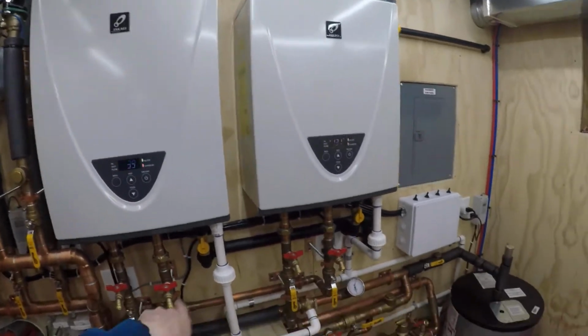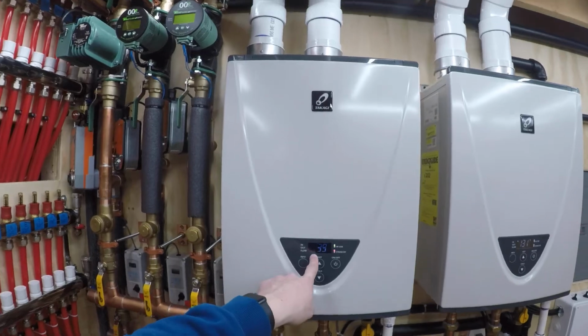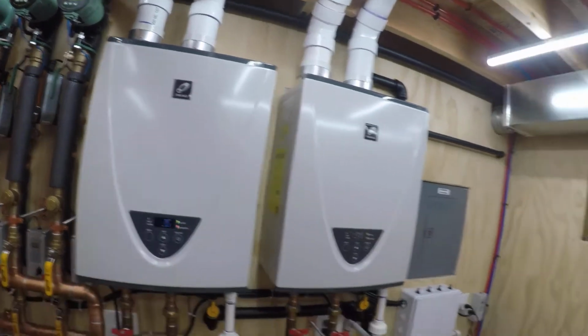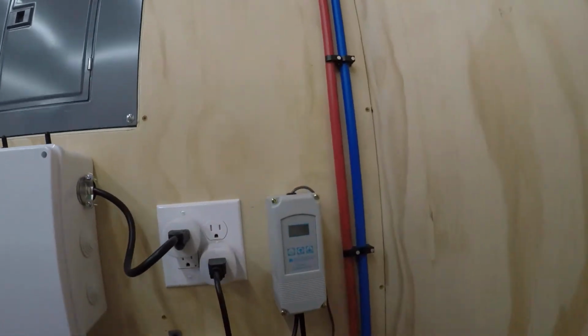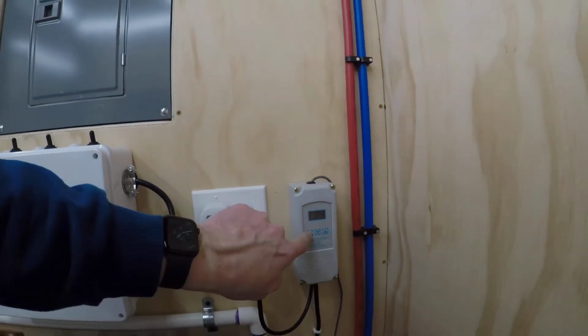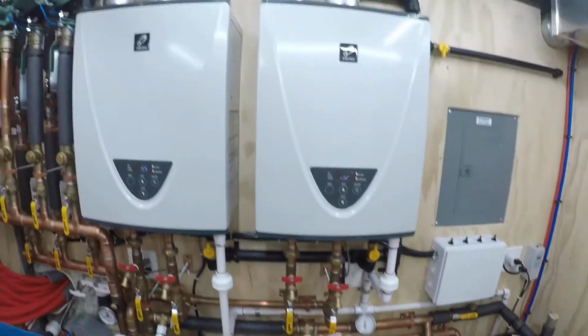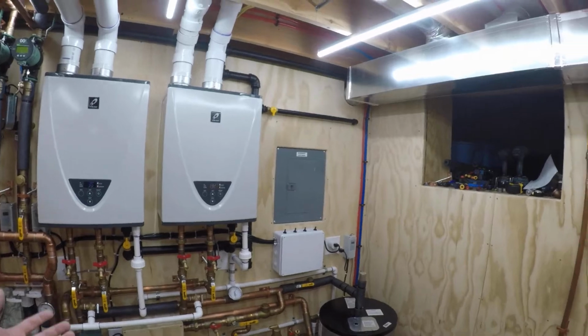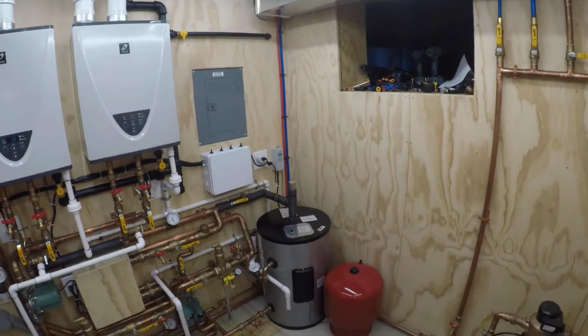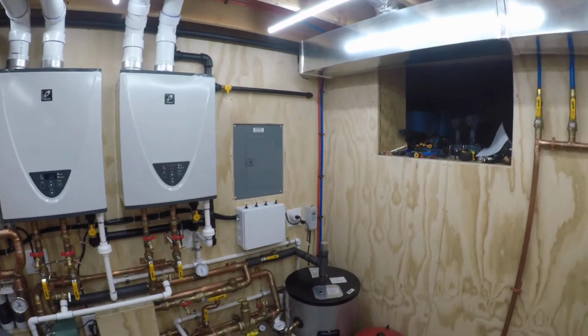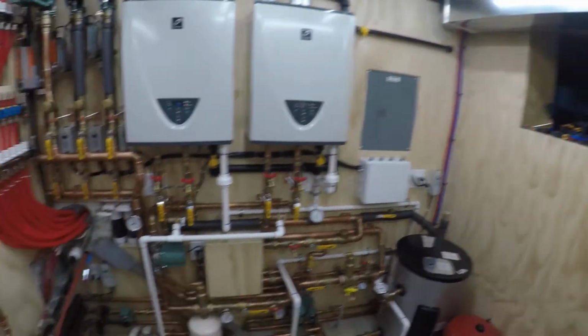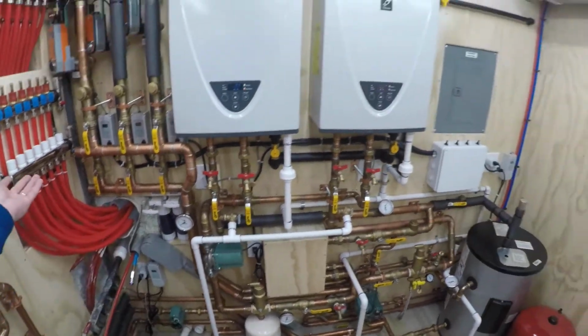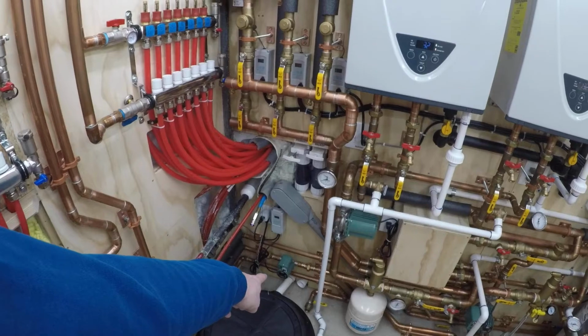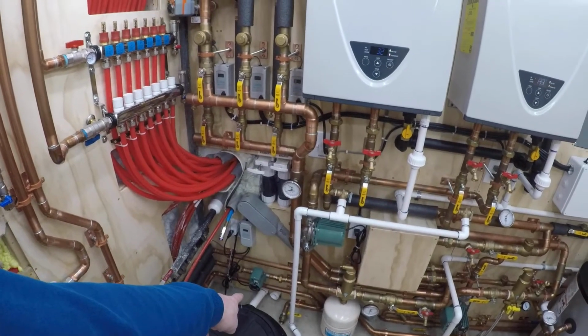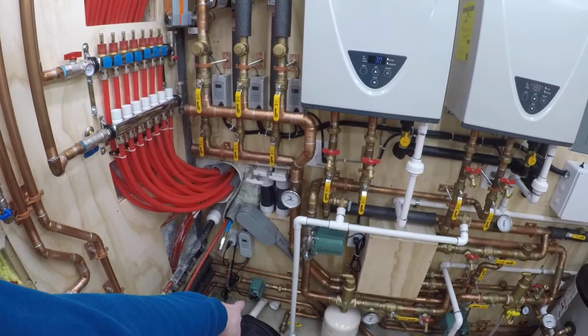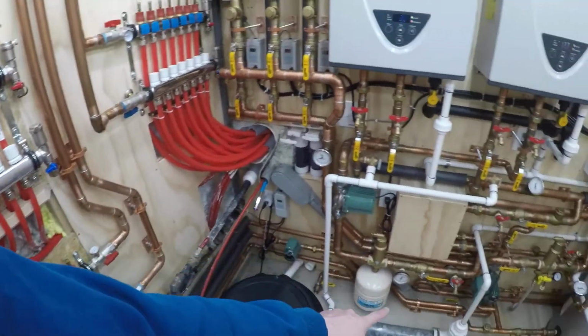So as the return water increases, because it's heating that tank, my BTU usage drops down. So as you'll see here, these are going to kick off once this aquastat hits 131 degrees, because that's what I set it at. It will shut off that pump and it will shut off the heaters. It takes about 3 minutes for that to occur. And during the normal day when there's no hot water draw, just with the recirc pump running, usually that thing runs for about 30 seconds every hour, maybe every 40 minutes or so, that'll kick on and keep that hot water loop hot.